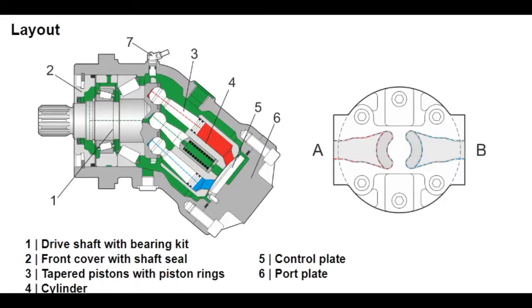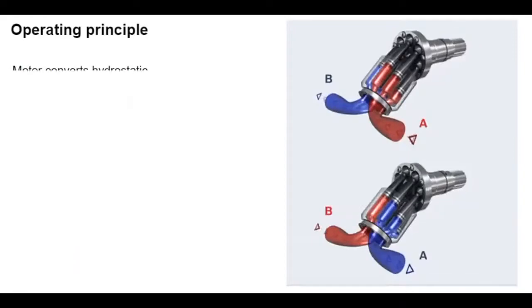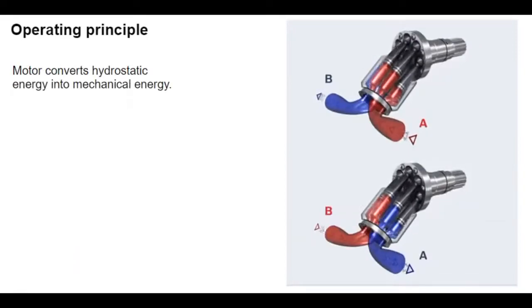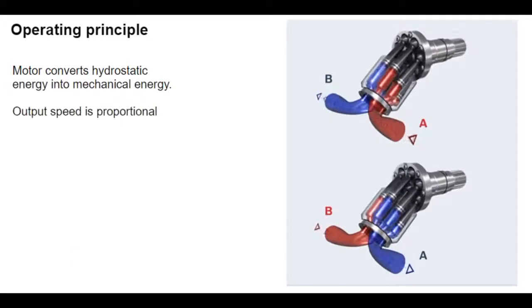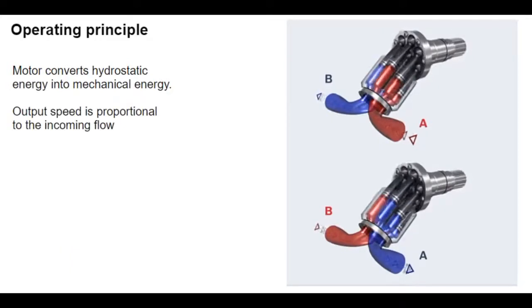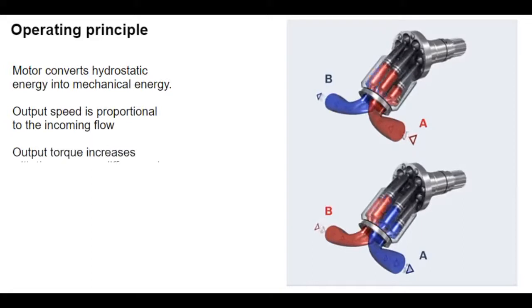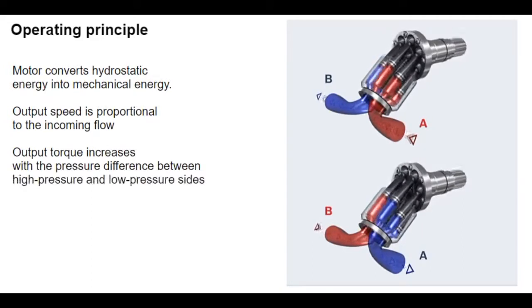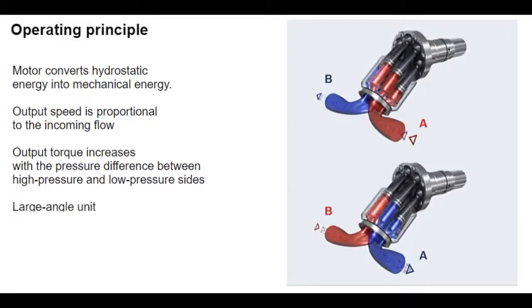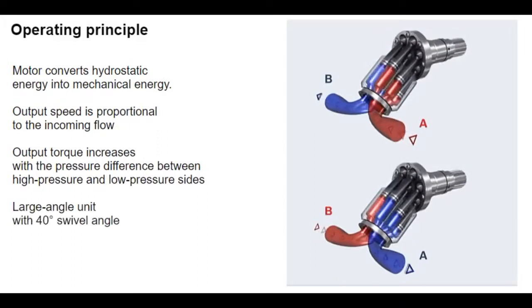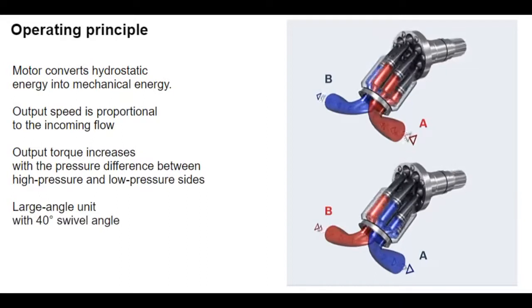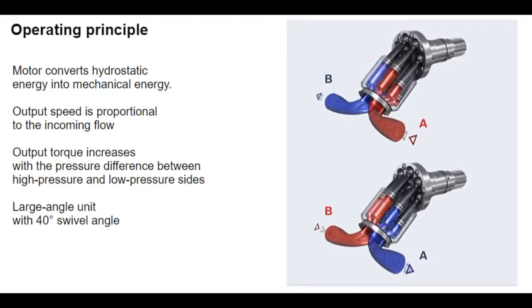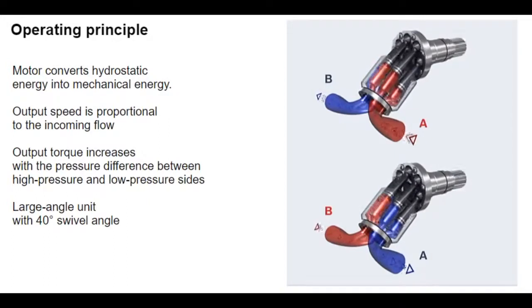The hydraulic motor can also be equipped with a speed sensor as an option. The cylinder bores are supplied with hydraulic fluid through the port plate and control plate. The pistons in the cylinder bores extend, which is converted into rotation at the driveshaft flange. The pistons also catch the cylinder and generate output torque at the driveshaft. Output torque grows with the pressure difference between the high-pressure and low-pressure sides. The output speed is proportional to the inward flow and inversely proportional to the displacement of the hydraulic motor.